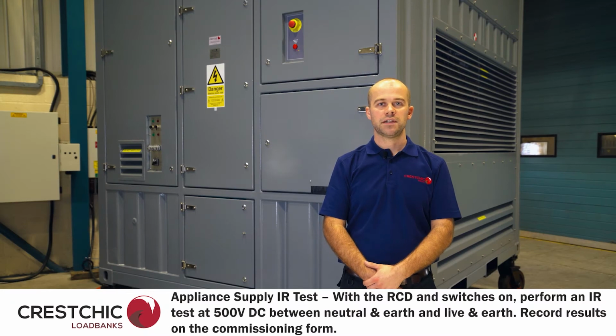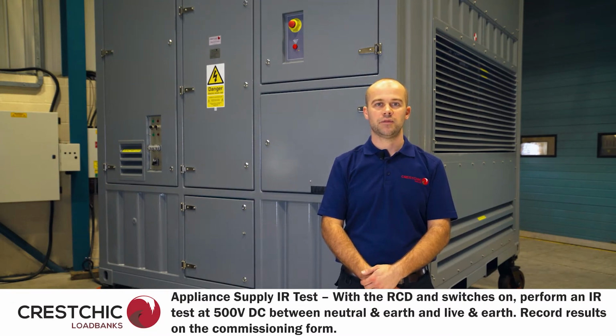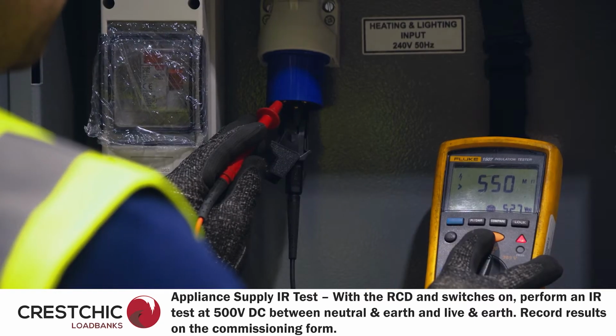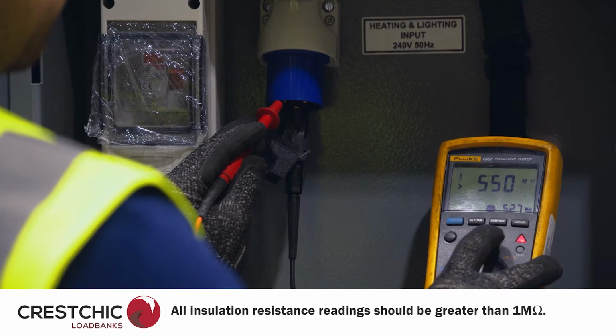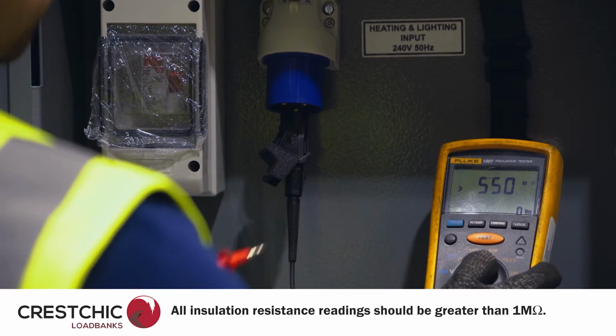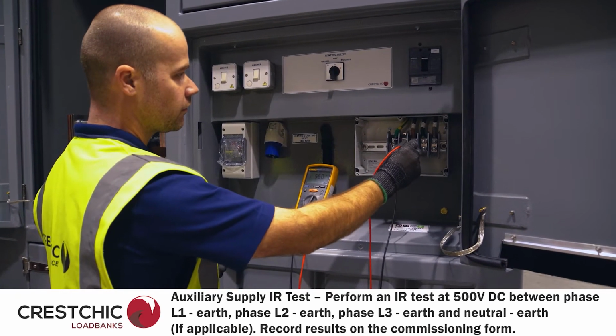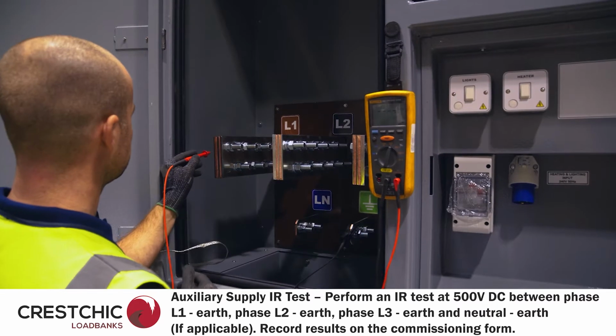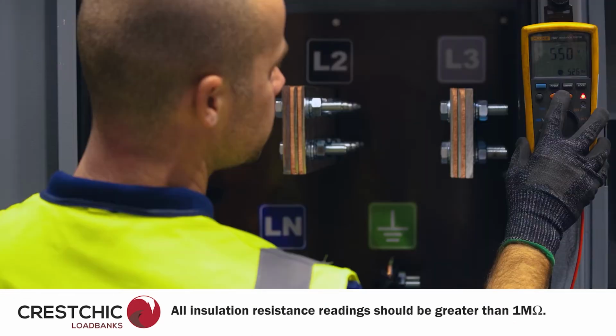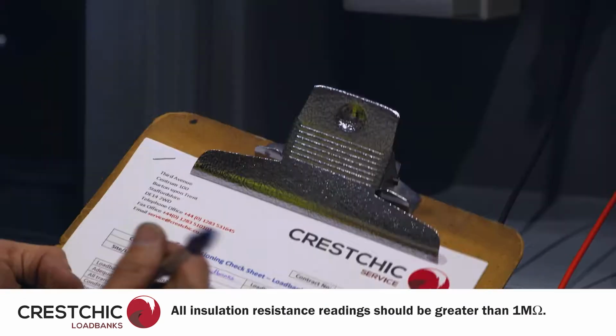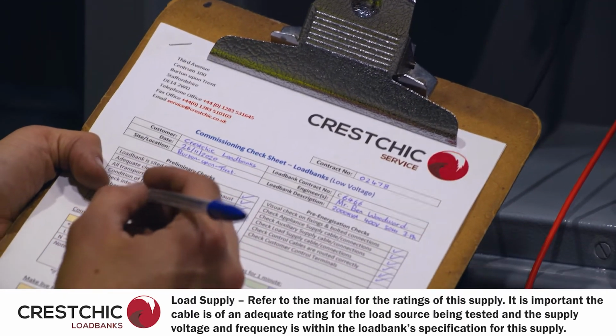Using an insulation resistance meter, the insulation resistance should be taken on all supply connections on the load bank. Typically, the load bank has an appliance supply input for the anti-condensation heaters and lights, an auxiliary supply input for the load bank control circuit, and of course the load supply. The insulation resistance should be measured and then recorded on the commissioning form.